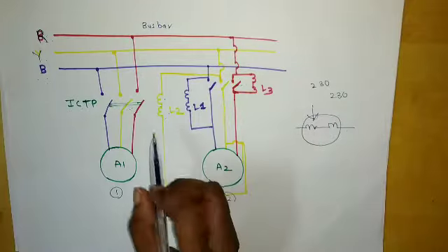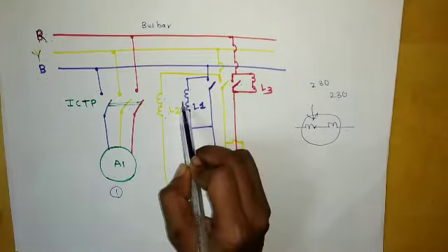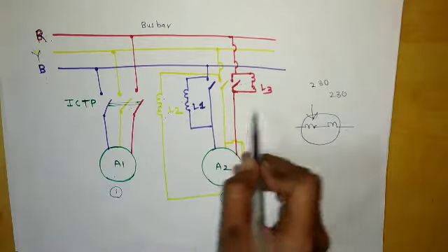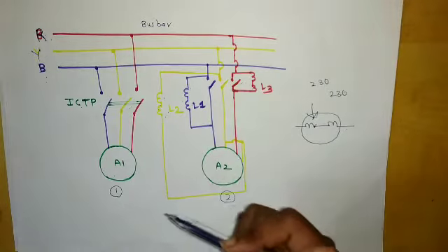If the phase sequence is not okay, this lamp will glow, then that lamp, and afterwards the other, with no similarity. There must be similarity: all three lamps must glow at the same time and dim at the same time. That means our phase sequence is correct.